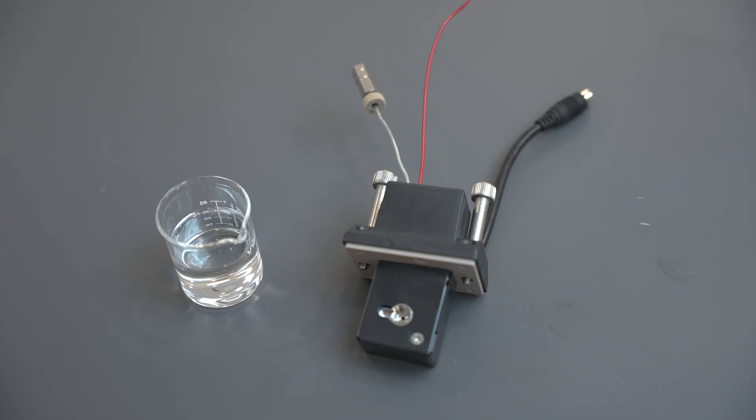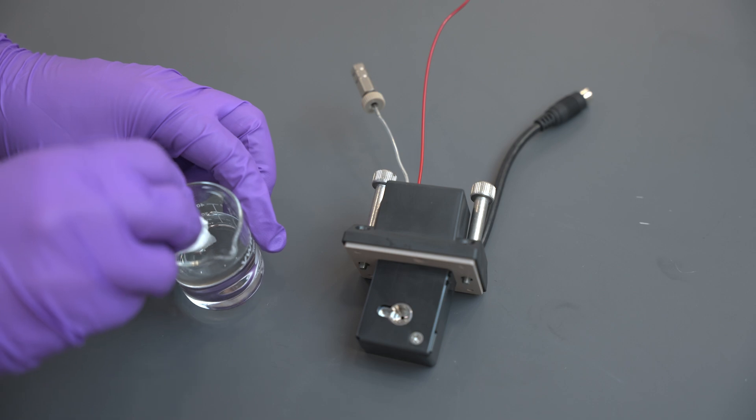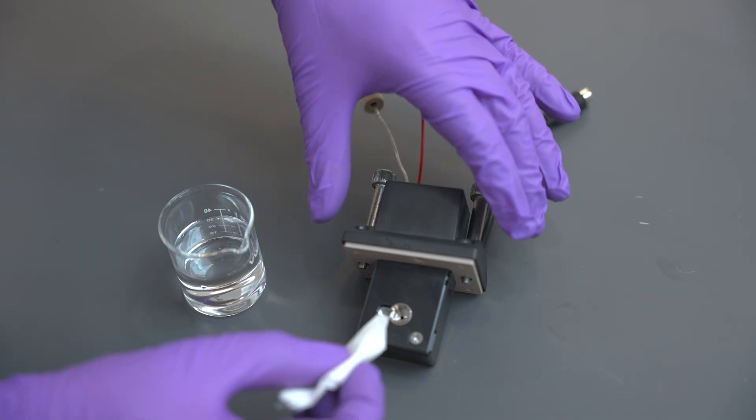Take a piece of wiping paper soaked in 2-propanol and wipe the inside of the flow cell where the lens and gasket sat.